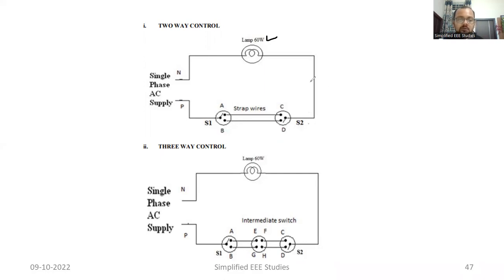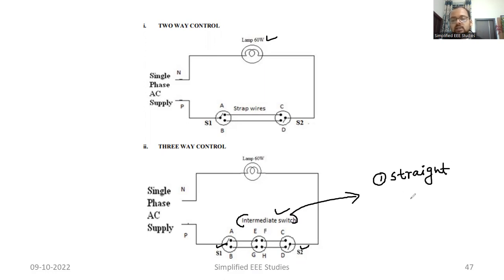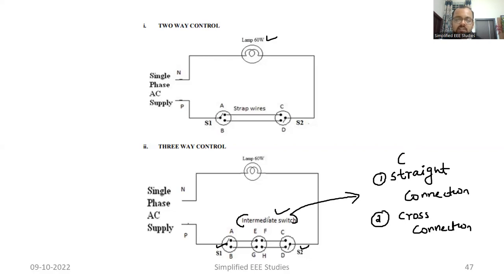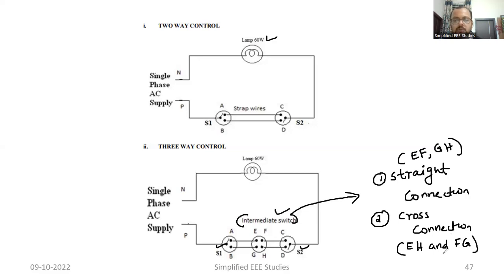You can see we have three switches. S1 and S2 are normal type of switches. Apart from that, we have one intermediate switch. The intermediate switch has two positions or two conditions. One is called straight connection and the other is called cross connection. In case of straight connection, EF and GH are in contact. In case of cross connection, EH and FG are in contact. This point you have to remember — straight connection and cross connection.